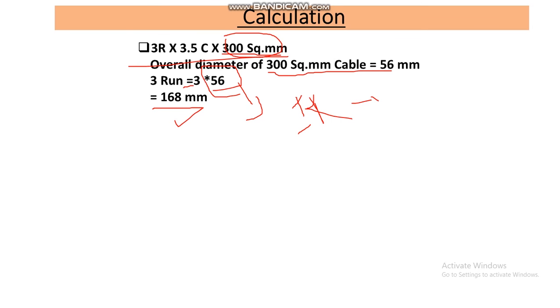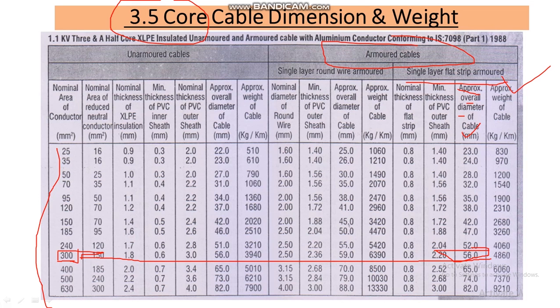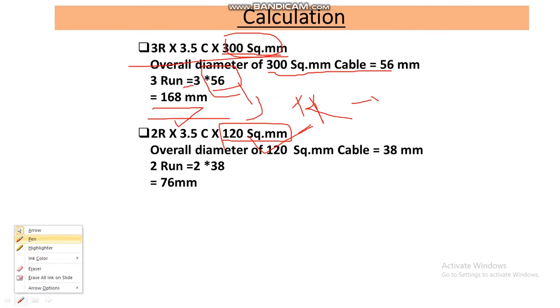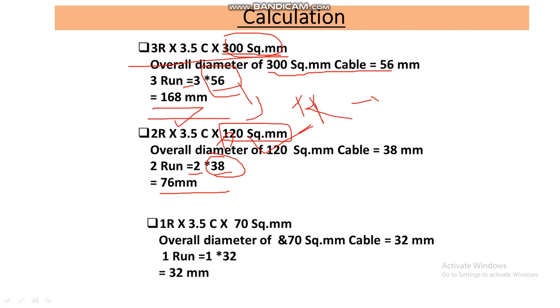Now for the two runs of 3.5-core 120mm² cable, let's go back to the cable catalog. Looking at the 120mm² entry, the diameter of this cable is 38mm. So for two runs, we multiply: 2 × 38mm = 76mm.